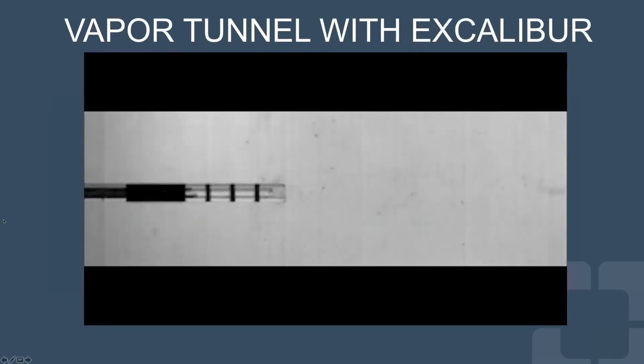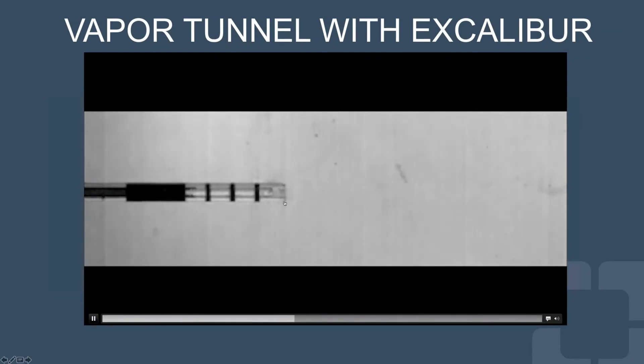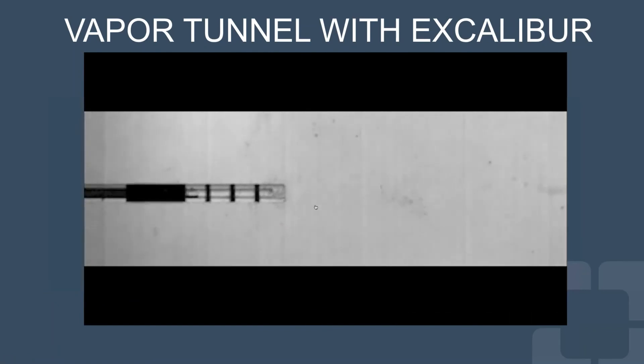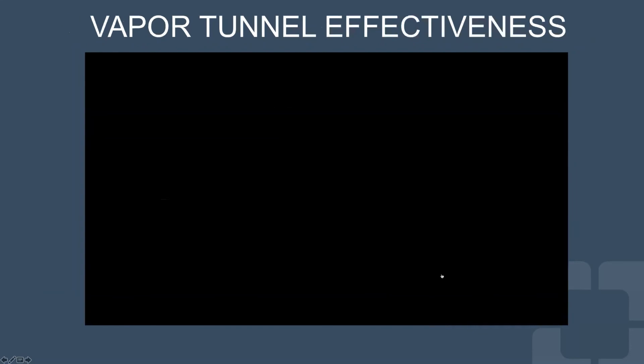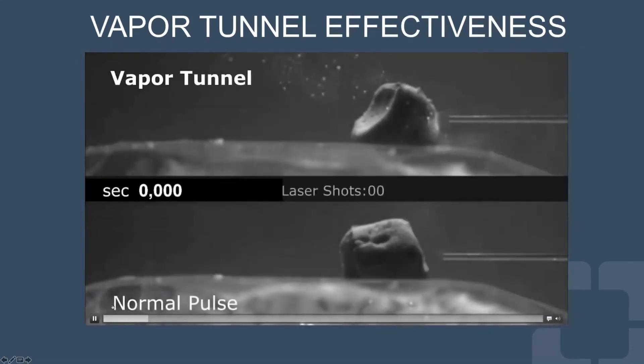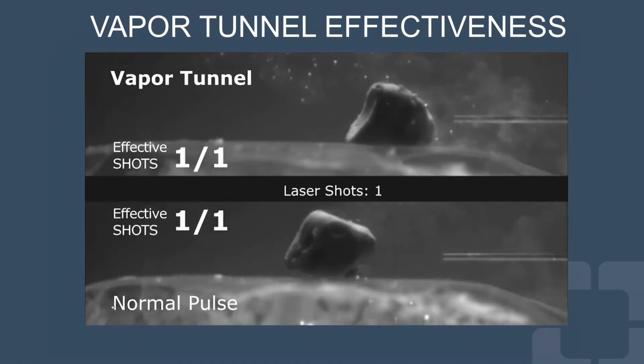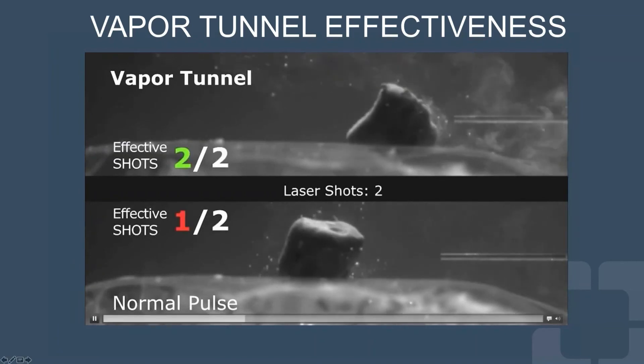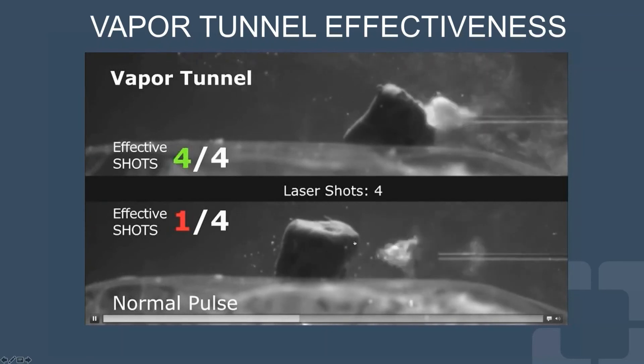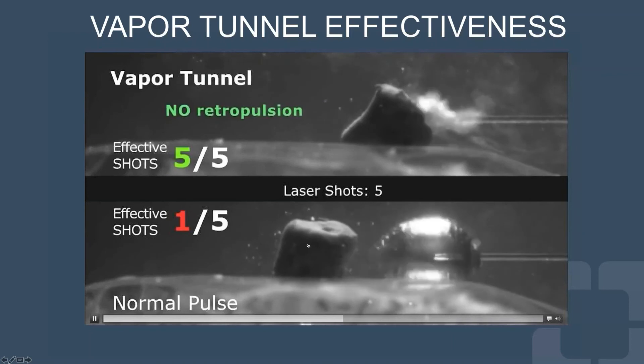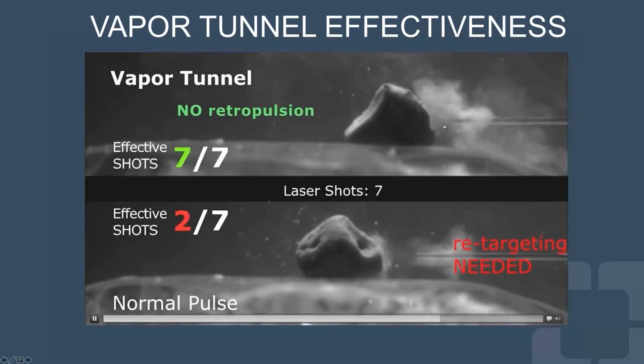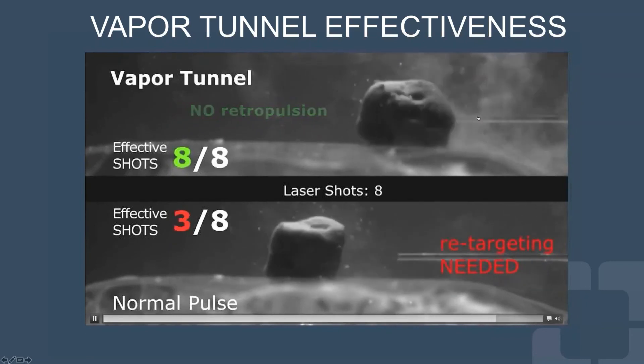Here's a video illustrating how the vapor tunnel works with the Excalibur fiber. You can see the pulse generates an elongated bubble, and the fiber tip is recessed from the sheath. Another video compares a normal pulse versus a vapor tunnel pulse: in the lower video, there is significant retropulsion for each pulse, and once the stone moves away, you lose effective shots with no more fragmentation. With the vapor tunnel effect, the stone stays put and you don't have to retarget — nine out of nine shots are effective versus only a fraction with standard pulsing.